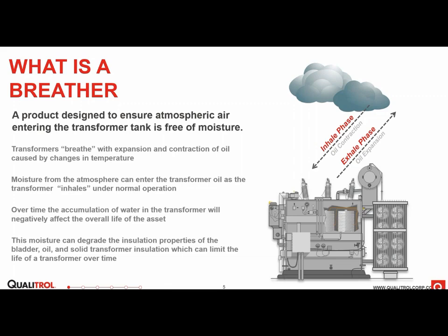So without a breather, the moist atmospheric air can enter into the transformer and then it can saturate the oil. And if that moisture saturates the oil, it can break down things like the bladder, the insulation properties of the oil, and the solid transformer insulation around the windings, and all of this can limit the transformer's expected lifespan.